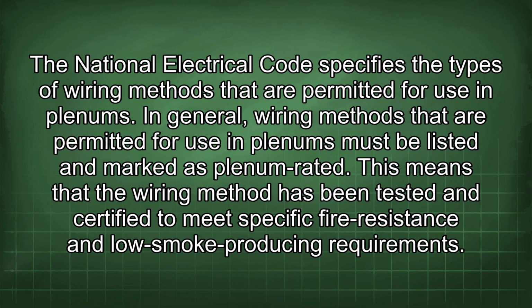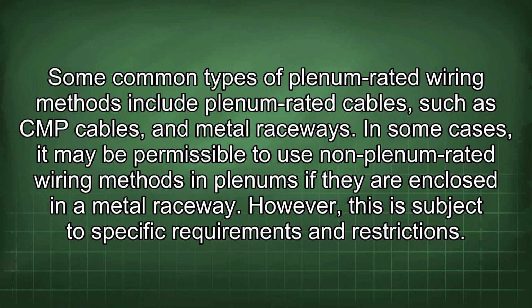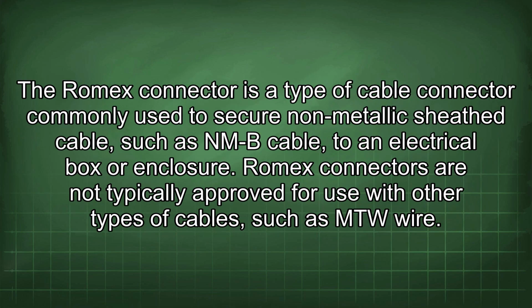In general, wiring methods that are permitted for use in plenums must be listed and marked as plenum rated. This means that the wiring method has been tested and certified to meet specific fire resistance and low smoke producing requirements. Some common types of plenum rated wiring methods include plenum rated cables, such as CMP cables, and metal raceways. In some cases, it may be permissible to use non-plenum rated wiring methods in plenums if they are enclosed in a metal raceway. However, this is subject to specific requirements and restrictions. The Romex connector is a type of cable connector commonly used to secure non-metallic sheathed cable, such as NMB cable, to an electrical box or enclosure. Romex connectors are not typically approved for use with other types of cables, such as MTW wire.